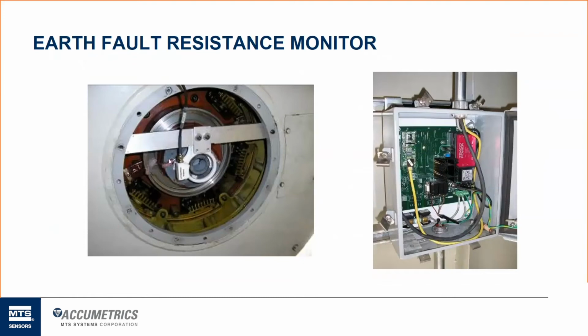You can see the gray transmitter is this piece that's mounted on the end of the rotor. There's a rotor end cap, which is underneath. This is all standard stuff that would already be on any smaller air-cooled unit, and we can easily adapt our transmitter right in the center line, so that eliminates any balance issues, any concerns with high-speed vibration and things like that. We mount it right to the end of the shaft, and then we install the stationary pickup antenna, which is this white ring antenna.